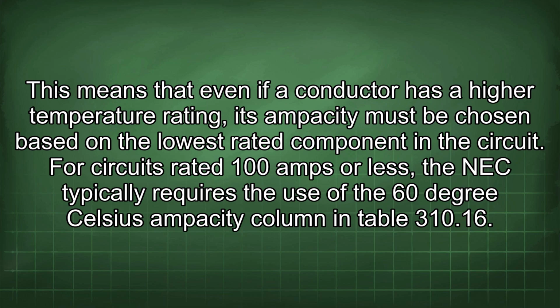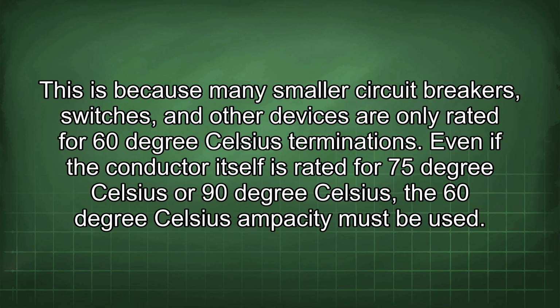For circuits rated 100 amps or less, the NEC typically requires the use of the 60 degrees Celsius ampacity column in Table 310.16. This is because many smaller circuit breakers, switches, and other devices are only rated for 60 degrees Celsius terminations. Even if the conductor itself is rated for 75 degrees Celsius or 90 degrees Celsius, the 60 degrees Celsius ampacity must be used.